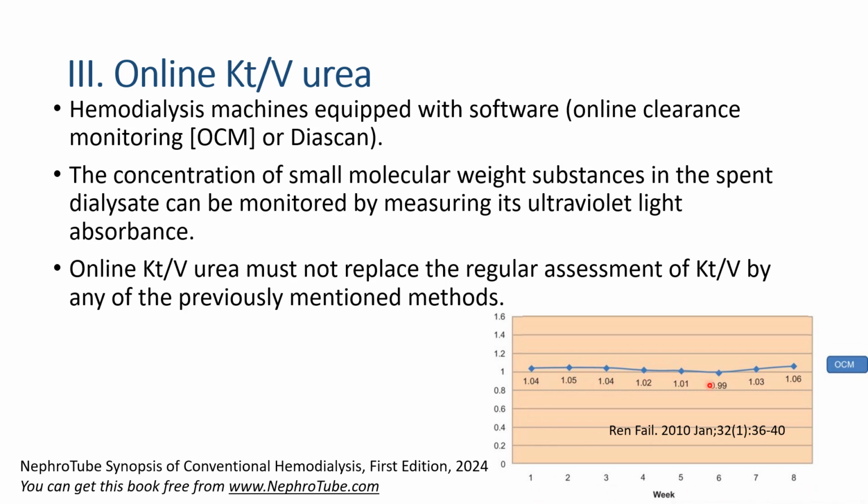This is the KT/V measured by the machine, and compared it with the actual delivered KT/V of the patient. Actually, there is a difference between both of them. So the online KT/V can give you a rough estimate about the KT/V of the patient, but it must not replace the regular assessment and measuring of KT/V.